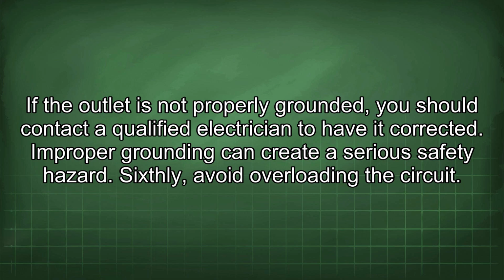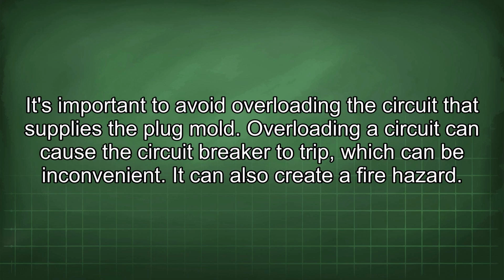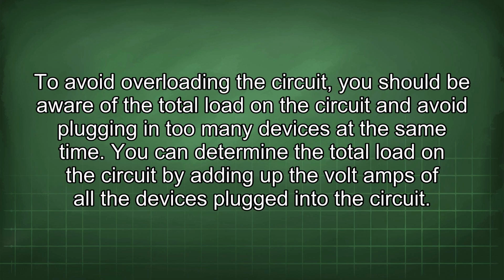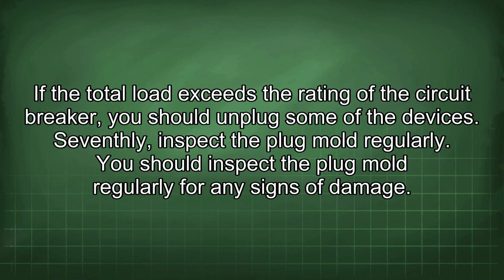Sixthly, avoid overloading the circuit. It's important to avoid overloading the circuit that supplies the plug mold. Overloading a circuit can cause the circuit breaker to trip, which can be inconvenient. It can also create a fire hazard. To avoid overloading the circuit, you should be aware of the total load on the circuit and avoid plugging in too many devices at the same time. You can determine the total load on the circuit by adding up the volt amps of all the devices plugged into the circuit. If the total load exceeds the rating of the circuit breaker, you should unplug some of the devices.